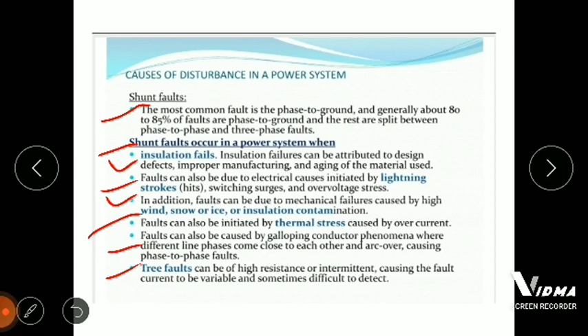Then we understand the fault statistics. It includes the type of fault and the percentage of severity of occurrence in a power system transmission line. We must understand that most of the faults in an electrical utility system with a network of overhead lines are phase to ground faults, resulting primarily from lightning induced transient high voltages and also falling trees and tree limb contacts, as already discussed in the previous slide.